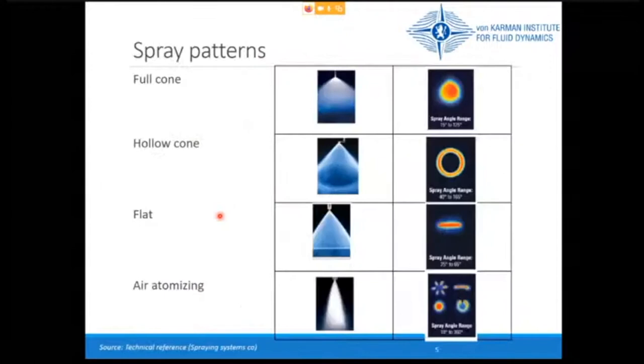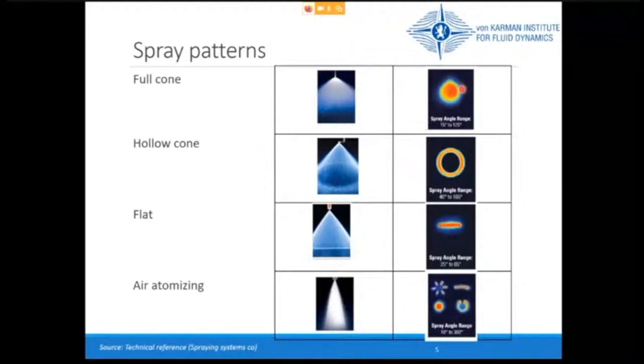Depending on the geometry of the nozzle, you can create different spray patterns. One mostly applied for water curtains is the full cone — from the side it looks like a cone, and from the bottom the water fills the whole cone. You can also have a hollow cone, where the water only fills the envelope. A flat pattern produces only a linear impact from the bottom. With air atomizing, more complex shapes are possible.